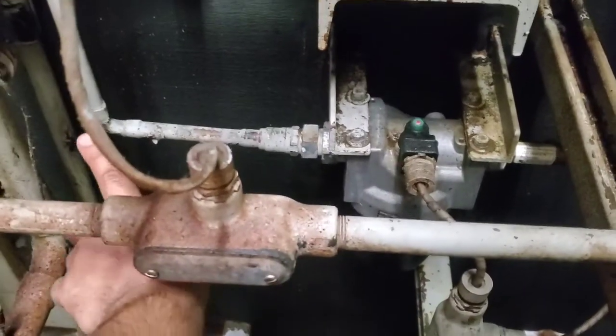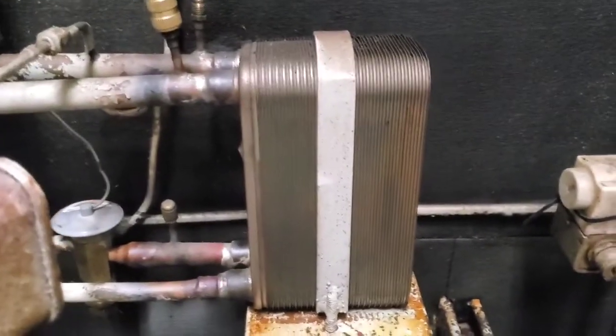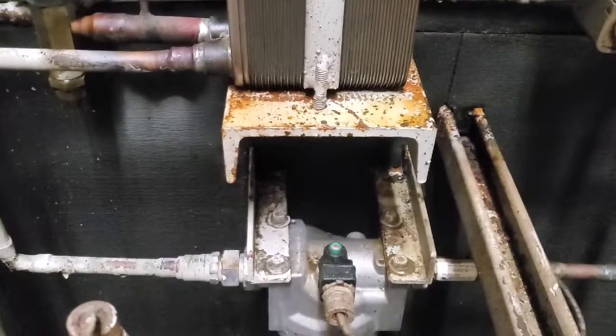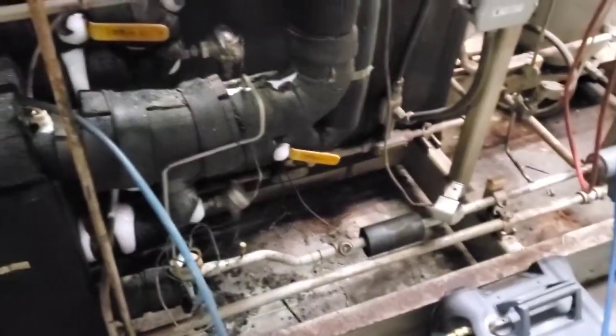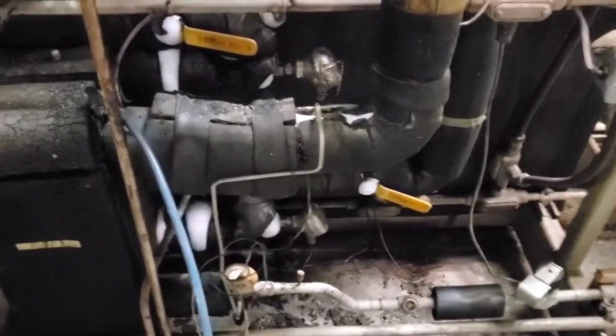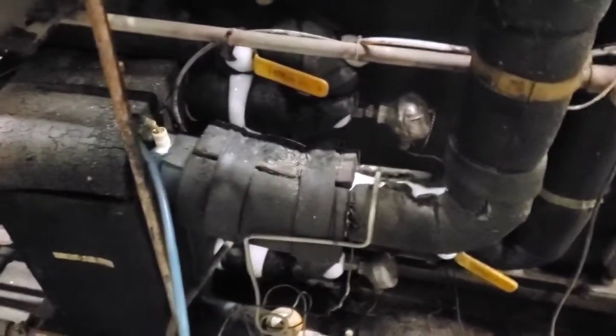This whole line that I'm pointing to goes to a heat exchanger that's filled with oil. So we can't just recover what's in this line because our recovery machine will not recover oil. So here's the plan. We're going to use the push-pull method. We're going to use our recovery machine and pull some suction gas out of that circuit, pump it through our recovery machine at a higher pressure.